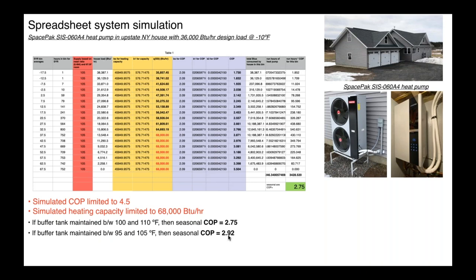We're still not taking advantage of outdoor reset. And the reason we did that in this particular system is that we're using that water in the buffer tank to provide most of the heating for domestic water. It doesn't provide 100%, but we're using that temperature range, 105, 110, to get most of the temperature lift for domestic water. Is that the optimal way to do this? I can't answer that yet. I've got to extend the spreadsheet and actually model that. In other words, are you better off to use outdoor reset control and have less preheating effect on domestic water, or as we have it set up right now?